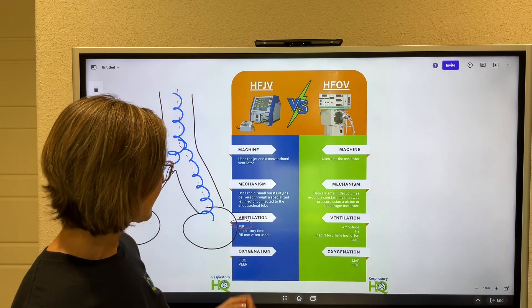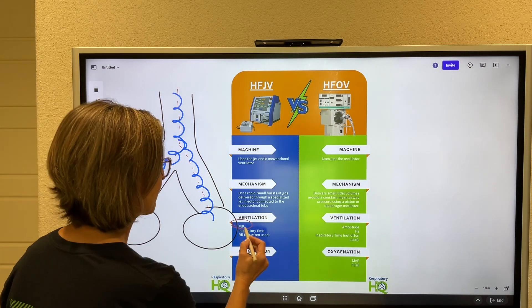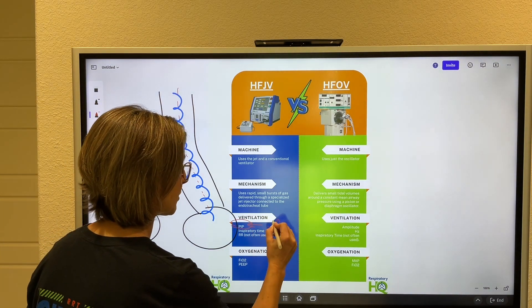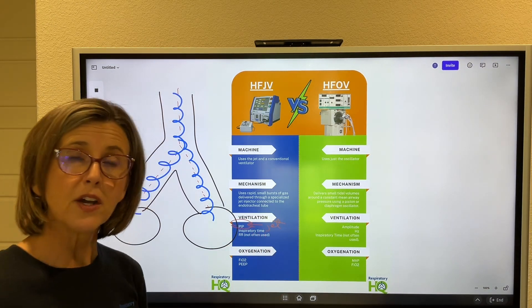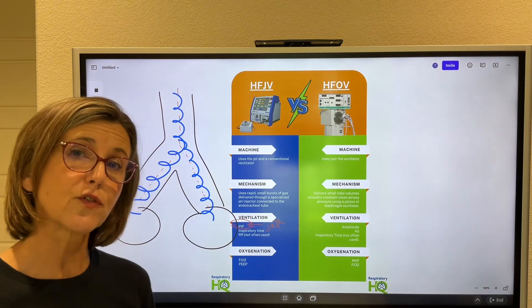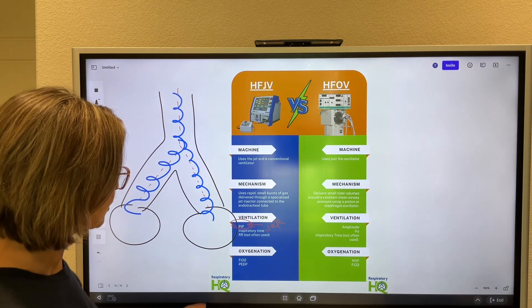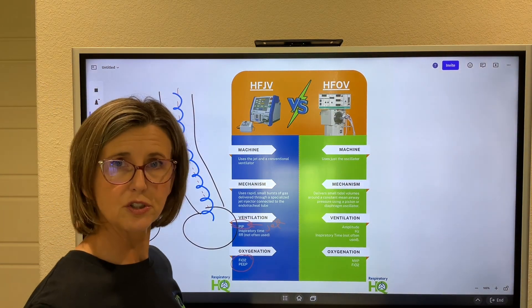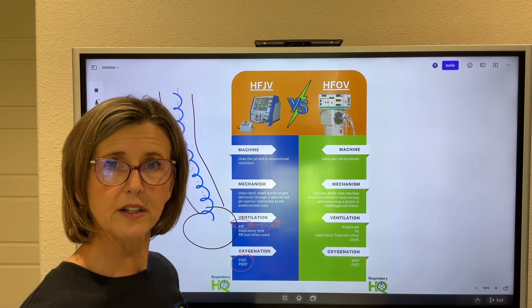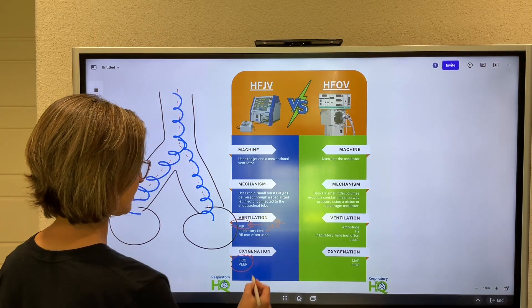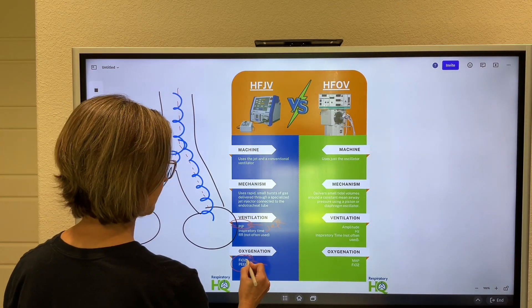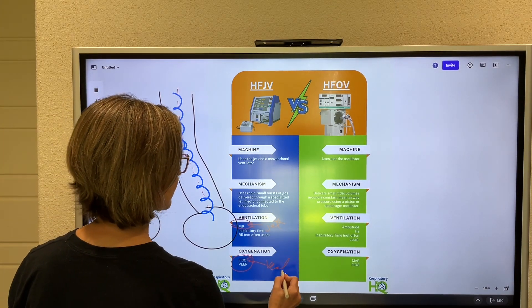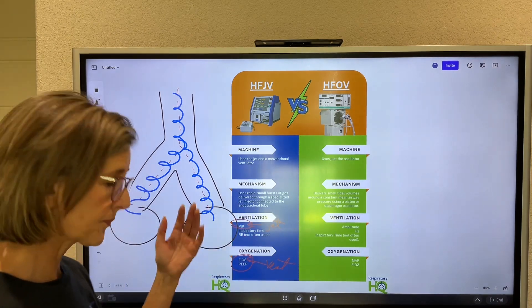When adjusting ventilation on the jet ventilator, remember that PIP is controlled by the jet. Oxygenation is adjusted by changing FiO2 and PEEP — just like conventional ventilation. But remember, FiO2 and PEEP are controlled by your conventional ventilator in this setup.